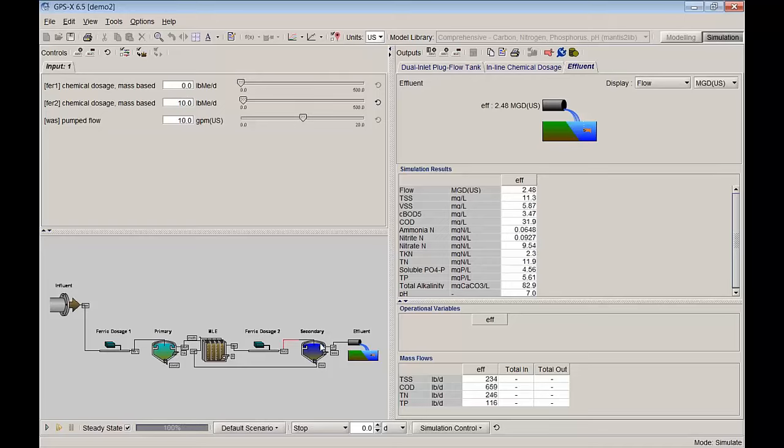And you can see here that has practically no effect on the amount that's out there. But if I start to put that up, we can see the effect. This is now dosing just at this particular point in the process here. And now we've knocked that 4.8 down to 2.3. And then I can continue to add here.